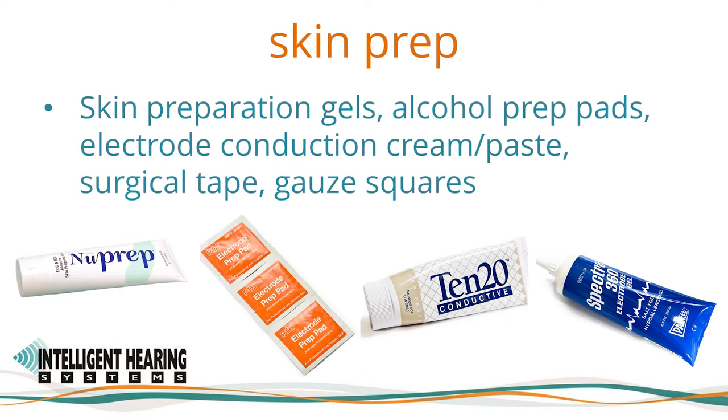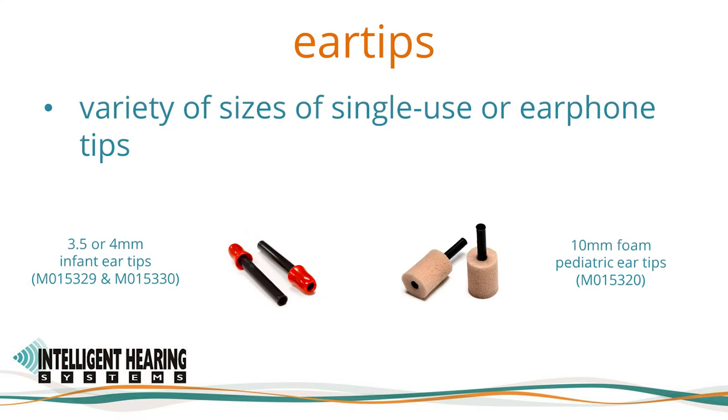Electrode prep creams such as NuPrep or electrode prep pads can be used to prepare the skin for electrode application. For centers required to use single-use items for skin preparation, we highly recommend the electrode prep pads pictured here. More than an alcohol pad, these pads have pumice which helps reduce impedance. Ten20 conductive paste can also be used with reusable electrodes. EEG conductive gel such as spectrogel can be added to disposable electrodes to improve conductivity. For pediatric assessment, we offer a variety of sizes of single-use earphone tips, including 3.5 and 4 millimeter plastic infant ear tips for smaller ear canals and beige pediatric foam ear tips.